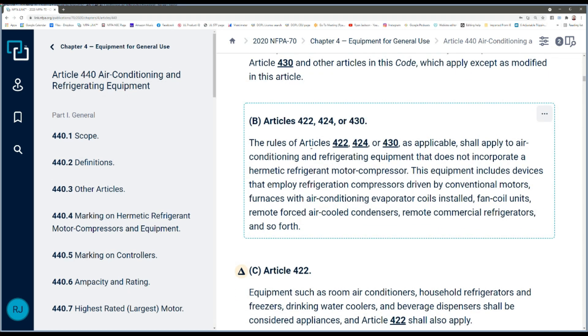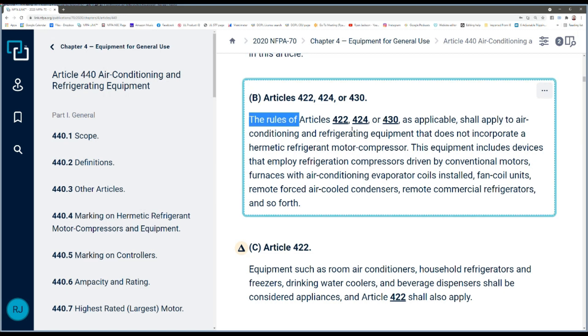This part is really important — subsection B: the rules of Article 422 (appliances), 424 (fixed heating), or 430 (motors) apply to air conditioning and refrigeration equipment that does not incorporate a hermetic refrigerant motor compressor. So at my house, I have a furnace — it's not regulated by Article 440, it's regulated by Article 422 as an appliance.